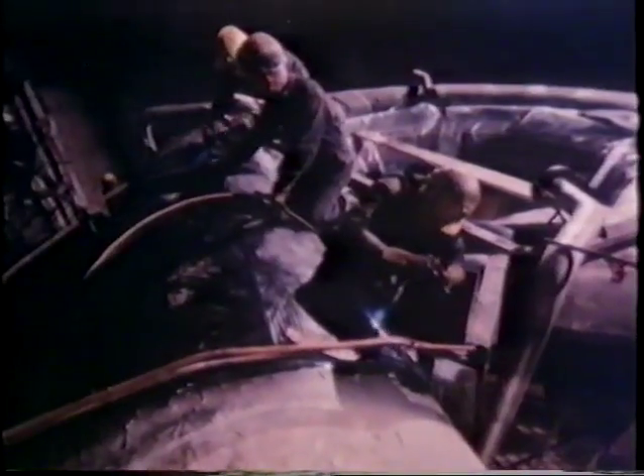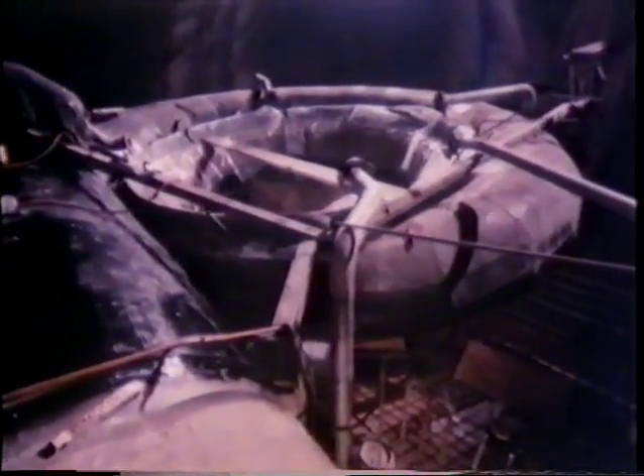The spiral case, fabricated from 1.5% manganese steel plate, is placed in position. The complete case and the pipe leading to it were tested to 70 kilograms per square centimeter. A resilient wrapping was applied to the spiral before it was encased in concrete to reduce vibrations and forces being transmitted into the building. The main reactions are carried into the structure by a collar on the inlet pipe and a deep skirt on the stay ring.